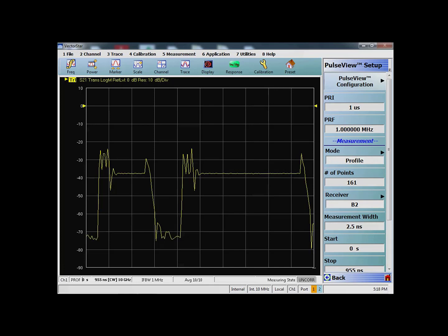In this particular demonstration, where we are using the pulse demonstration module, the A1 receiver is still getting a CW. That's because it's easier. But if you need a pulse modulator test set in place to give you RF pulsing, or say DC or IV pulsing, you can still use the pulse modulator test set, which I will show you in my next video.